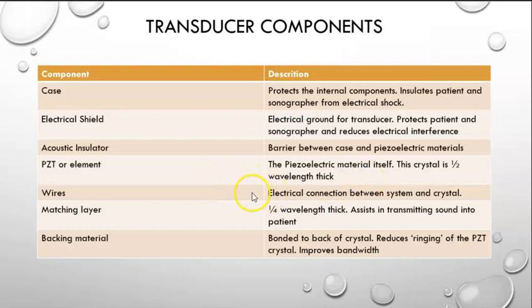The wires are simply electrical connections between the system and the crystal, and then we have the matching layer in the front. And as we said, the matching layer is a quarter, well, we didn't say, but I'm going to tell you. The matching layer is a 1/4 wavelength thick, and this assists in getting the sound into the patient. We'll describe why that is in just a moment here. And then we have the backing material, which reduces the ringing of the piezoelectric crystal, which improves what we call bandwidth, and we'll talk more about bandwidth in just a few minutes here.